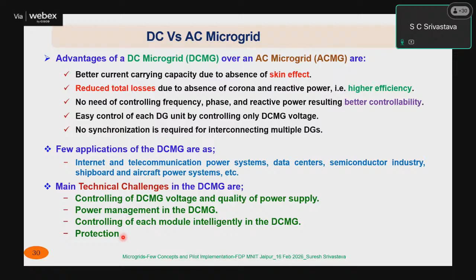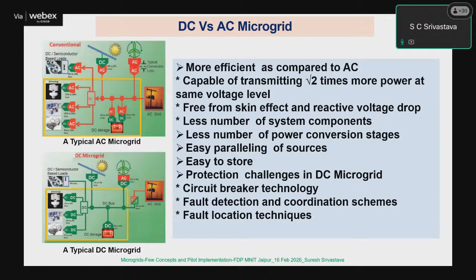Protection becomes an issue. I'll just tell you why. So, carrying forward, DC is more efficient as compared to AC, with the capability of transmitting root 2 times more power at the same voltage level. It is free from skin effect and reactive power, and has fewer system components, because the AC converter is not there. Paralleling of sources becomes easier here, whereas you have to go for synchronization and other requirements in AC. It is easy to store because DC can be stored directly in a storage system. But protection becomes very challenging because circuit breaker technology is not there. It is being developed. Fault detection and coordination is key. Fault detection becomes difficult, and location also has to be taken care of.